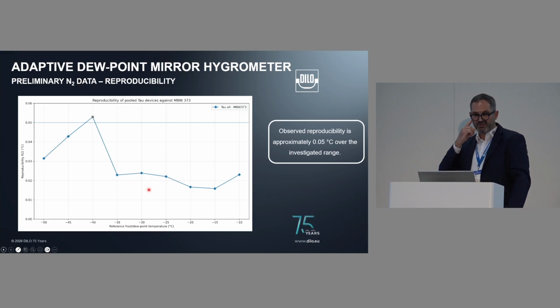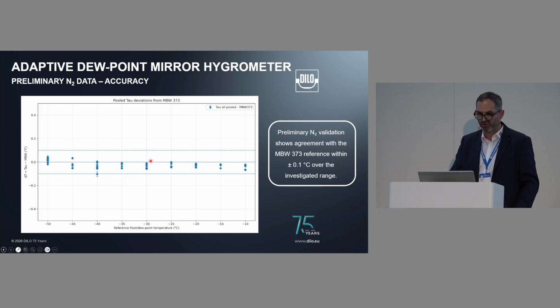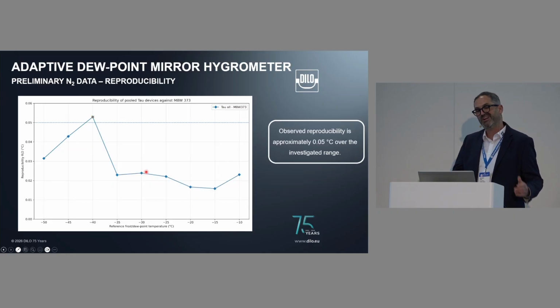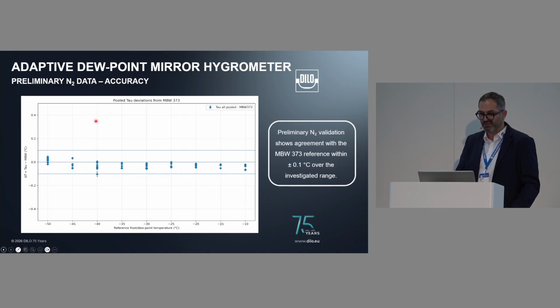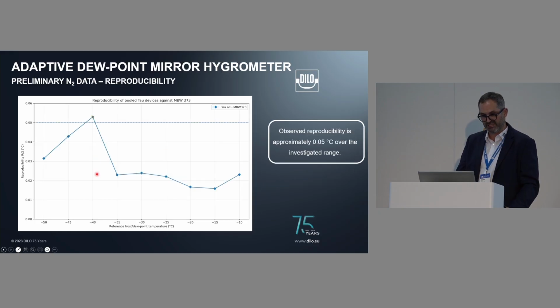Okay, and when we take the reproducibility, the reproducibility is determined basically by the maximum difference between the lowest and the highest point, and we divided it by a factor of 2. And this is the result here, for example. So all values are well below 0.05 degrees Celsius, except the one at minus 40. But I think if you would remove this, your result would definitely be inside that interval. But we are very close to that.